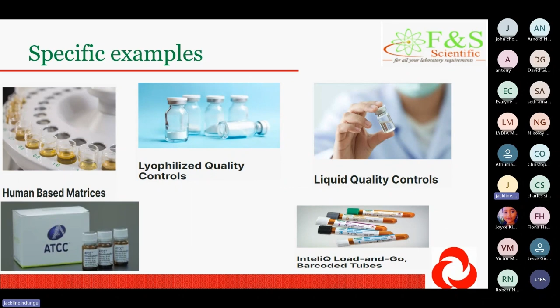I had also shared the InteliQ load, and this is also from Bio-Rad. These are whole blood, and they are used for things like blood bank. So how do you select your QC? My colleague will talk about the rules and Westgard and everything else. That is one area you also look at. You also look at the matrix. QC should mimic your patient samples. Most manufacturers will actually mimic the patient samples, so that is one area you don't struggle with because most of the manufacturers have really set that for you.